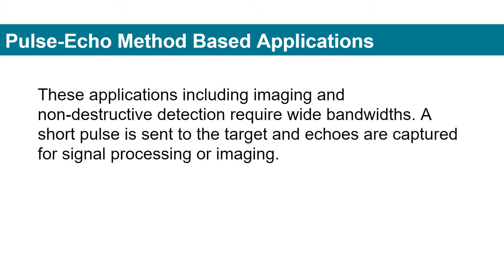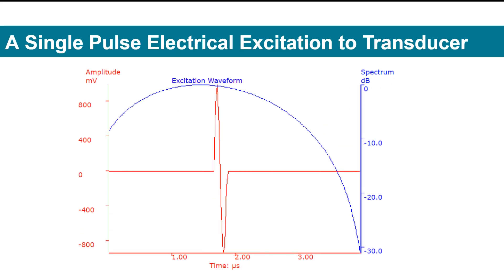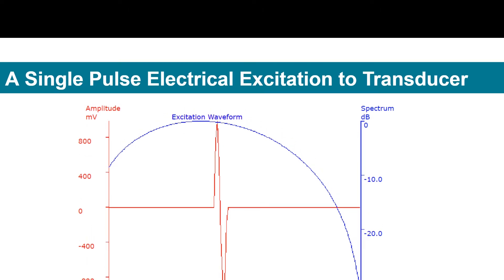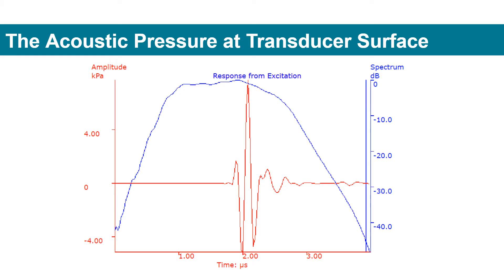Pulse echo method-based applications — including imaging and non-destructive detection — require wide bandwidth. A short pulse is sent to the target, and echoes are captured for signal processing or imaging. For example, when a single-cycle electrical pulse is applied to the transducer, ideally the output is also a single-cycle acoustic pulse. In reality, a much longer pulse with ring-down will be obtained instead.